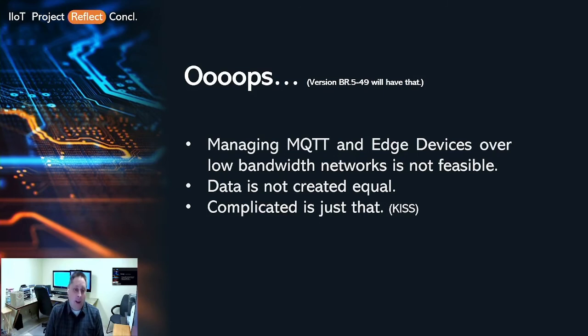The last drawback to edge devices is that you are adding layers of complication to something that was relatively simple in the past. If you're dealing with a centralized SCADA server and you're doing polling or looking for data, you're dealing with one server and you've got all your tags built up into it, and you can kind of do what you need to do to troubleshoot that.